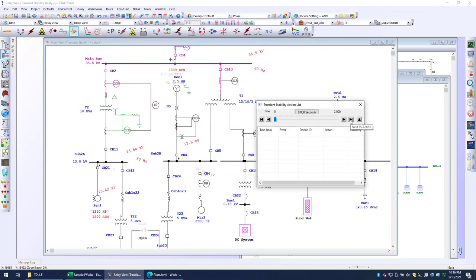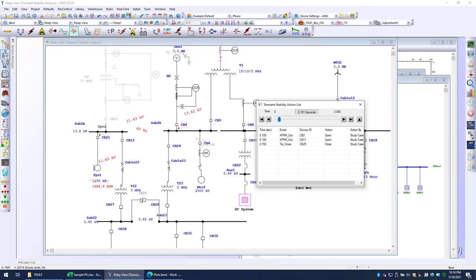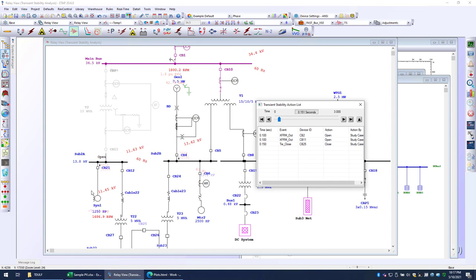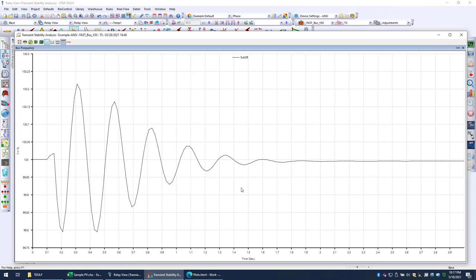All right, so here are the actions. There it is, opening of, isolating that transformer. This whole side becomes de-energized, that's why you see it green. And then 50 milliseconds later, that tie closes, restoring power to that critical load. So now let's take a look at what the bus frequency is for that particular location. We're going to open up the frequency graph for that.